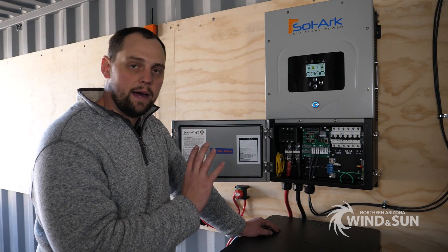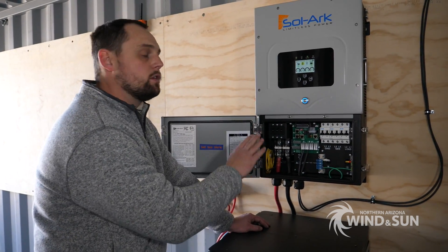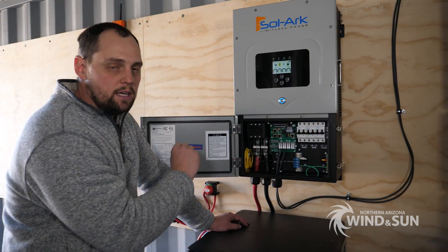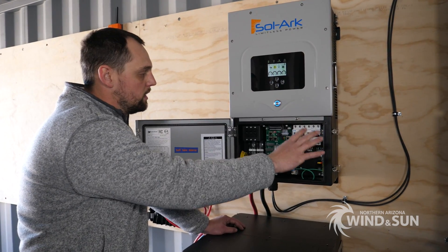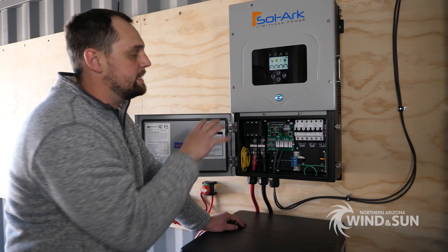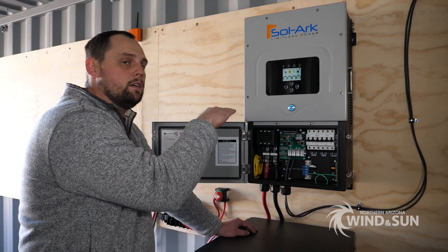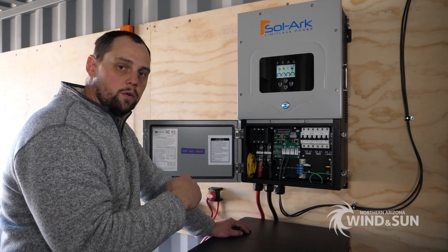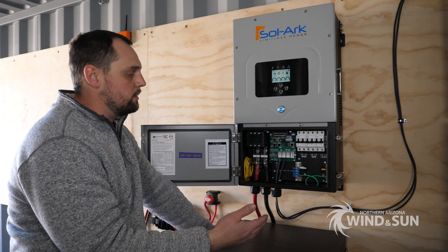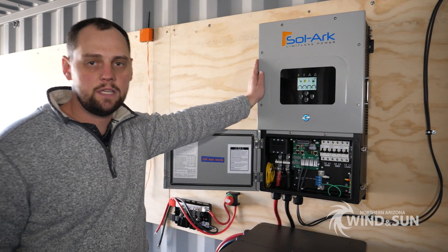The Sol-Ark has quite a lot of compatibility with a number of batteries on the market as far as closed-loop communications are concerned. These network cables allow you to parallel multiple Solarks together, and you can also connect batteries into the inverter's network. The batteries themselves will communicate to the inverter, telling it when they're willing to accept charge, their state of charge, and various other attributes of the battery's current state.